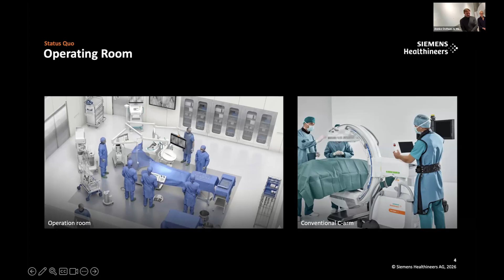They require manual positioning for every image. The technician, you can see him on the right behind with the tablet, brings and adjusts the system. The surgeon on the opposite side gives instructions and has no direct control over the X-ray device. So positioning and image parameters are controlled by the technician, and the surgeon looks at the monitors, which are quite small in conventional C-arms. The operation of the device is done with a tablet, which is for conventional C-arms quite outdated and cumbersome to use. This workflow is quite interrupting the flow of the surgery, as we have this dependency between the surgeon who wants to see an image and the technician who needs to deliver.